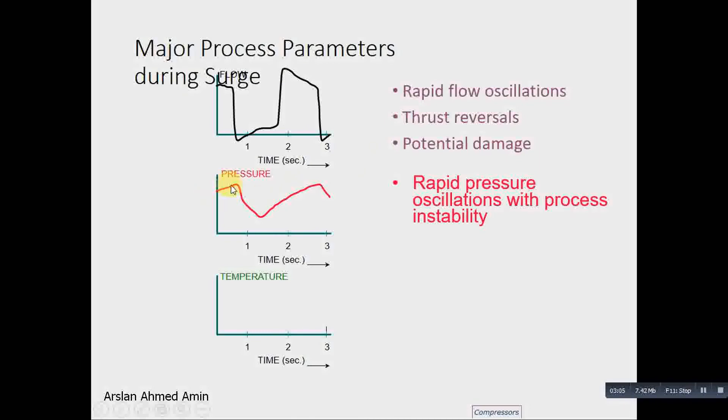We see rapid flow oscillations. In the surge condition, there are rapid flow oscillations, thrust reversals, and potential damage to the metallurgy of the compressor. The flow is greater and pressure is greater, but when the pressure reduces, the flow reverses, and then the pressure normalizes and oscillates. This is an oscillatory system.